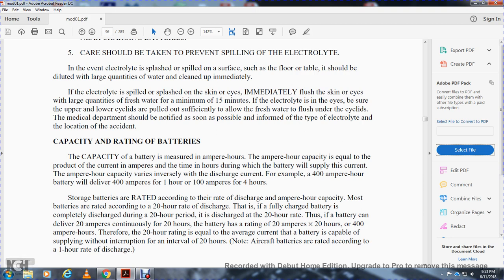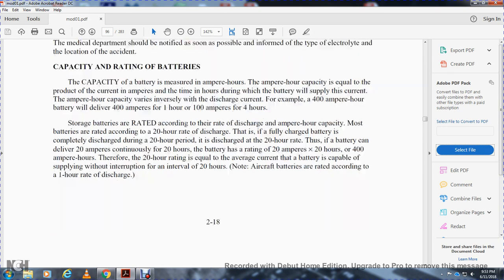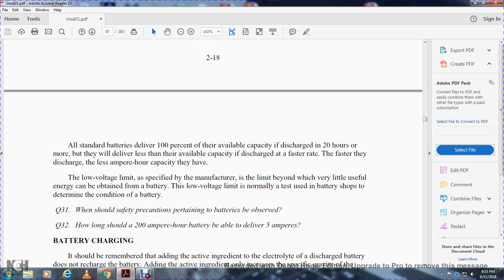The 20-hour rating equals the average current the battery is capable of supplying continuously over 20 hours. Note that aircraft batteries are rated according to a one-hour rate of discharge. All standard batteries deliver 100% of their available capacity when discharged over 20 hours or more; they deliver less than their available capacity when discharged at a faster rate. The faster the discharge rate, the lesser the ampere-hour capacity. A low voltage limit is normally used in battery shops to determine the condition of the battery.